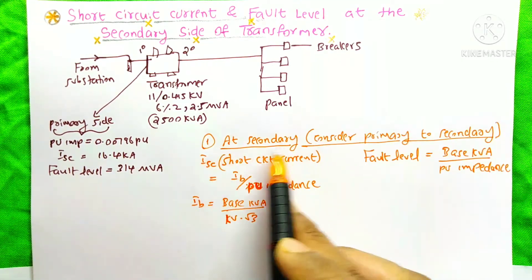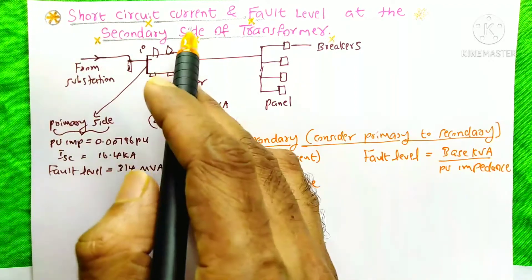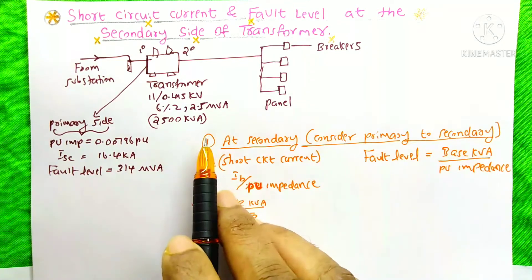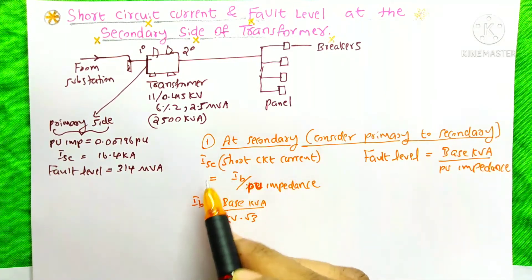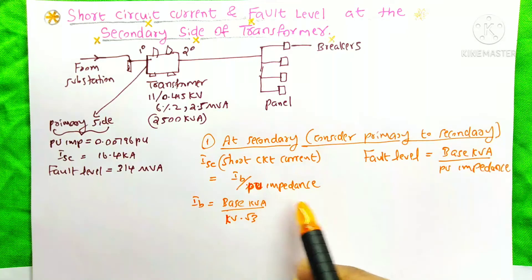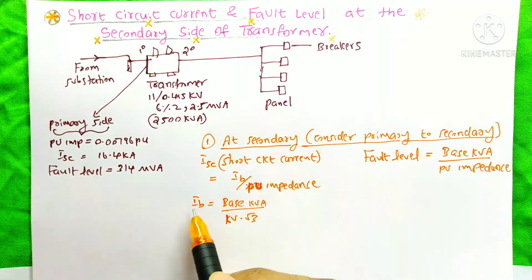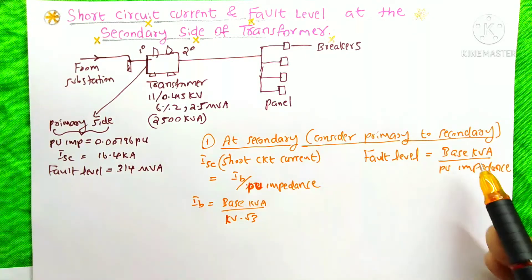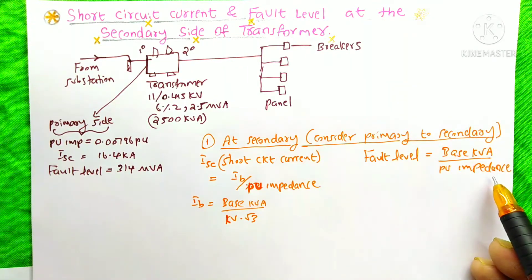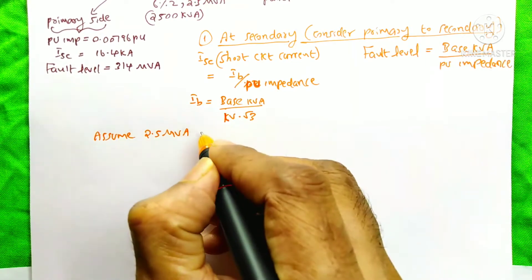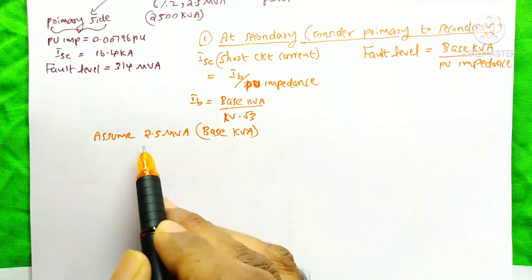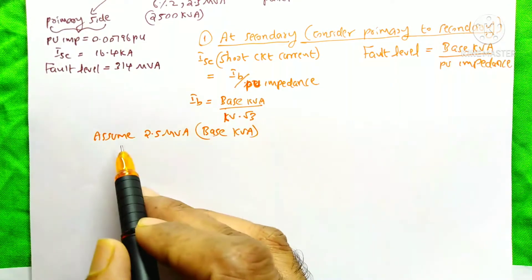First, we are going to calculate the short circuit current and fault level at the secondary side of this transformer. For that, we need to consider the primary to secondary side. The short circuit current equation is ISC equal to IB divided by per unit impedance, where IB is the base current. Base current equals base kVA divided by kV into root 3. The fault level equation is base kVA divided by per unit impedance. Here, we assume 2.5 MVA as our base kVA — the same as in the previous video. We need to assume the same base kVA everywhere in our calculation, otherwise the calculation will be wrong.